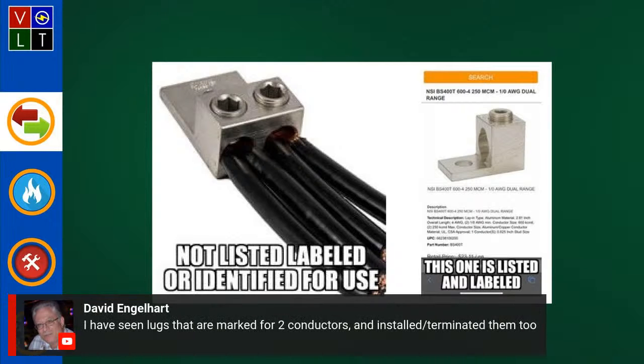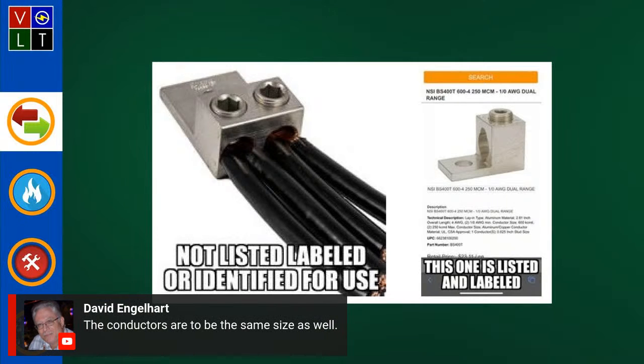Sure, one way you can tell is looking at the inside where you're going to make the termination, because the ones that are not listed for it are just completely round. The ones that allow it actually have a half circle above and below, so the conductors will seat in there and compress properly.